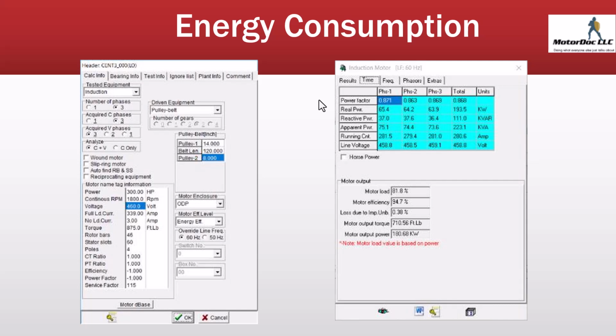So if we get into energy consumption, let's take a look at what the opportunities look like there. For instance, this one, you can see I've got my output kilowatts and my input kilowatts. So any losses inside the machine are going to be only up to about 13 kilowatts. And we find that interesting because some companies will claim these massive losses inside a machine. In reality, when we're looking at critical bearing issues, we're usually talking in terms of watts loss, even in a high-end machine like a 300 kilowatt.